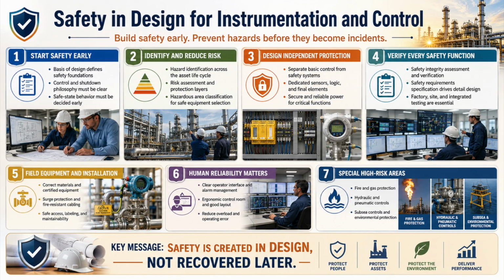Ask the harder questions. How does it fail? What happens when power returns? What if the sensor drifts? What if the operator is overloaded? What if a bypass remains active? What if the valve does not move? What if the cable burns? What if the supplier's standard package does not match the site? What if maintenance cannot safely reach the device? That is where real safety engineering begins.